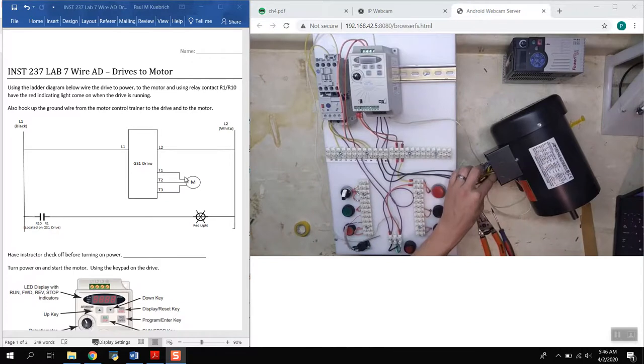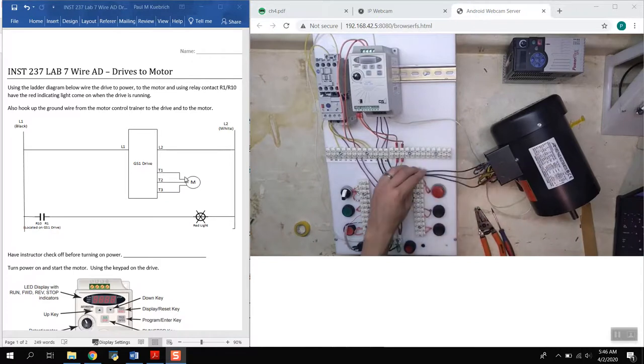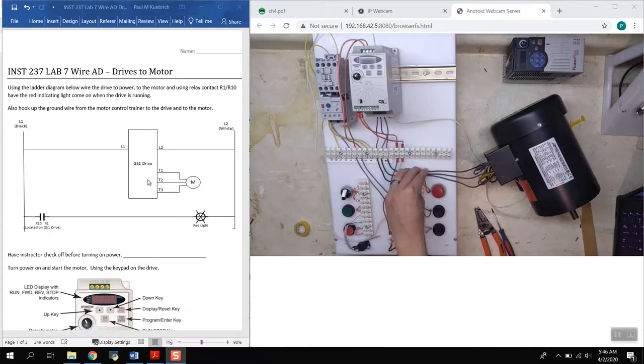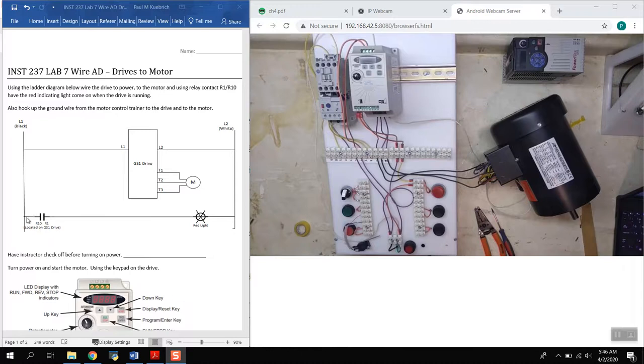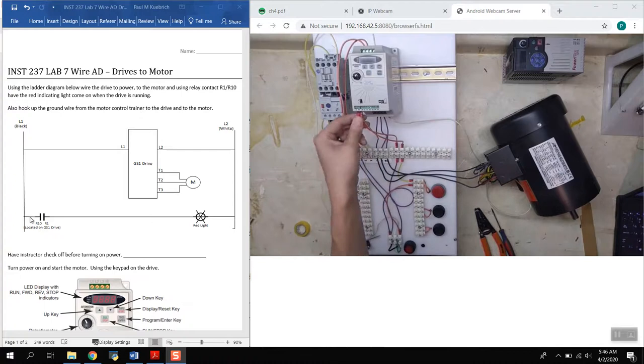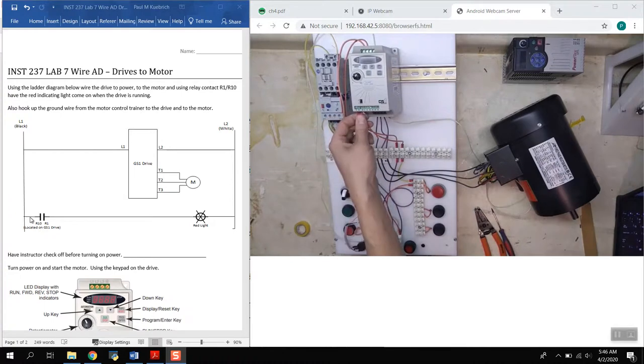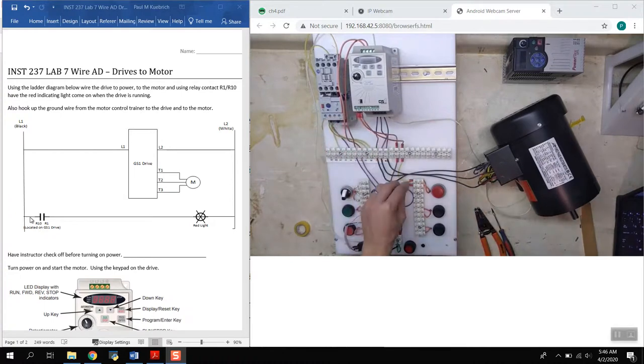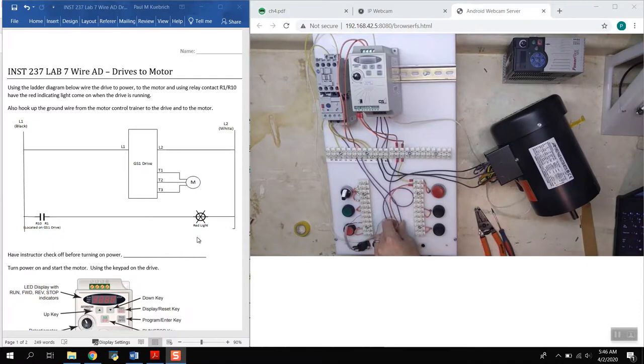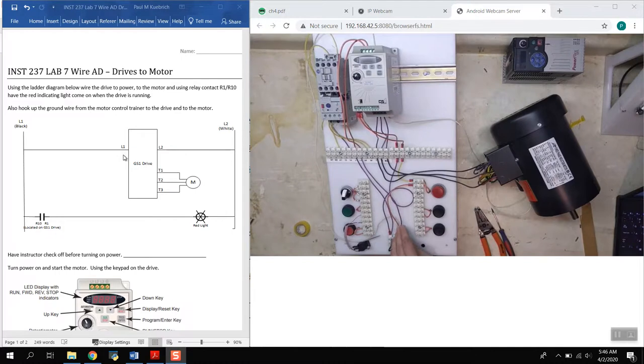So everything's connected for that, that takes care of everything up here for the L1, L2, T1, T2, and T3. The last thing that needs to be connected is coming in from again L1 our incoming power, going up through this purple wire with a loop on it, goes into R1 and then R10 comes out to a red pilot light and that goes down into L2.